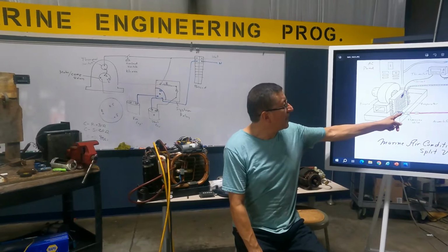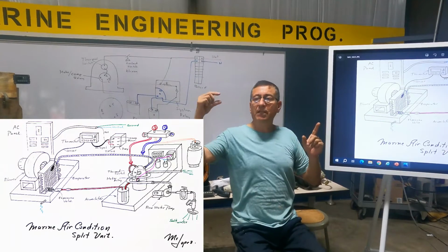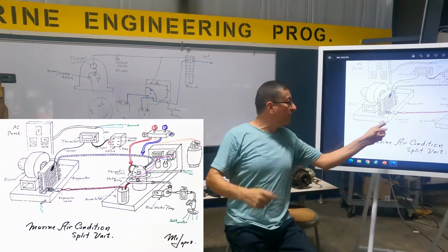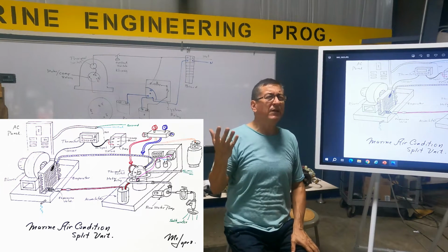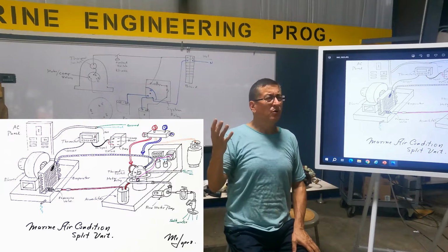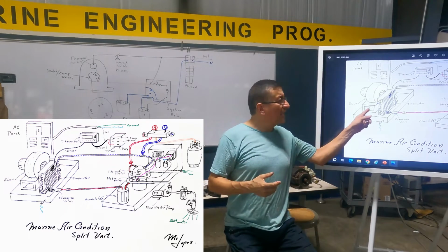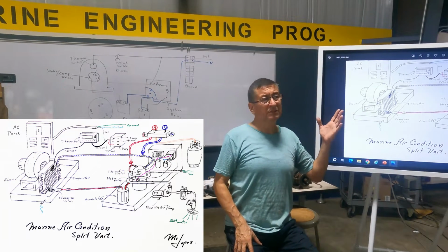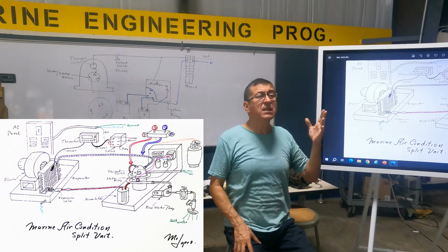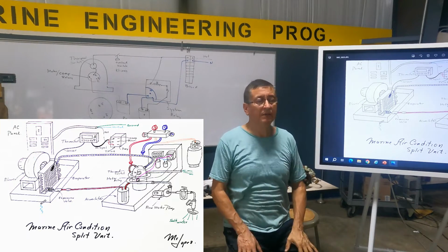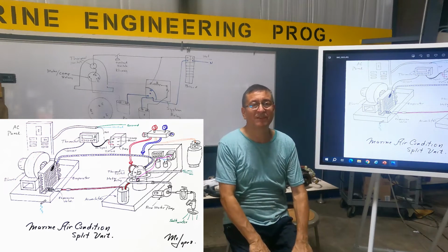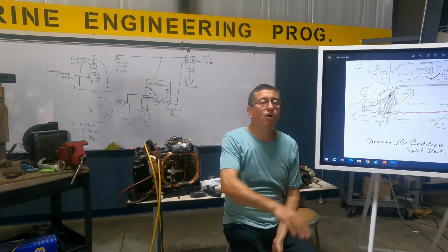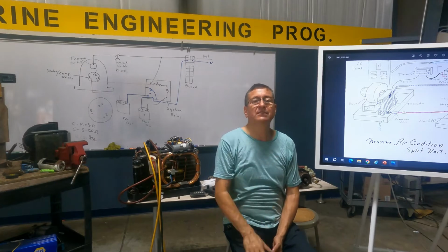After the capillary pipe, you remember the input pressure? 225, and the temperature around 110. After that, the pressure is around 70 psi and 40 degrees Fahrenheit. If you keep in mind those numbers, that's nice. That's universal; in all air conditioned units, it's exactly the same.